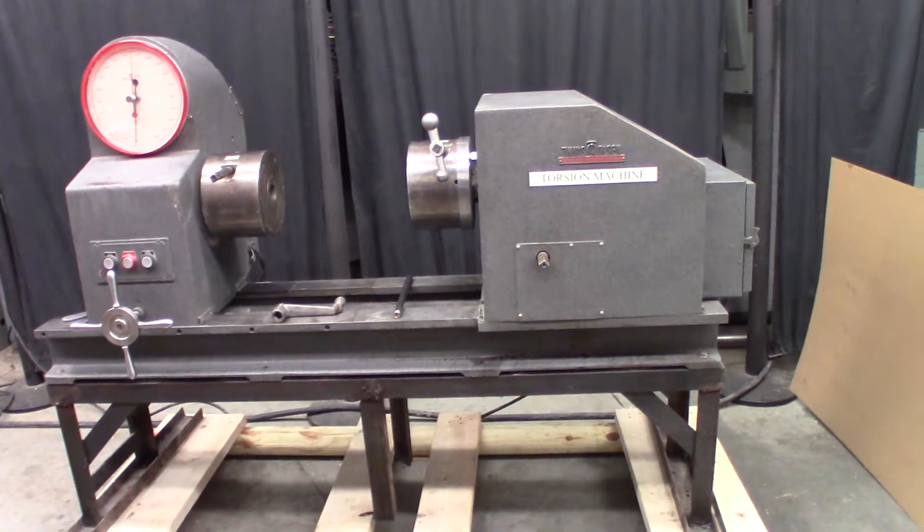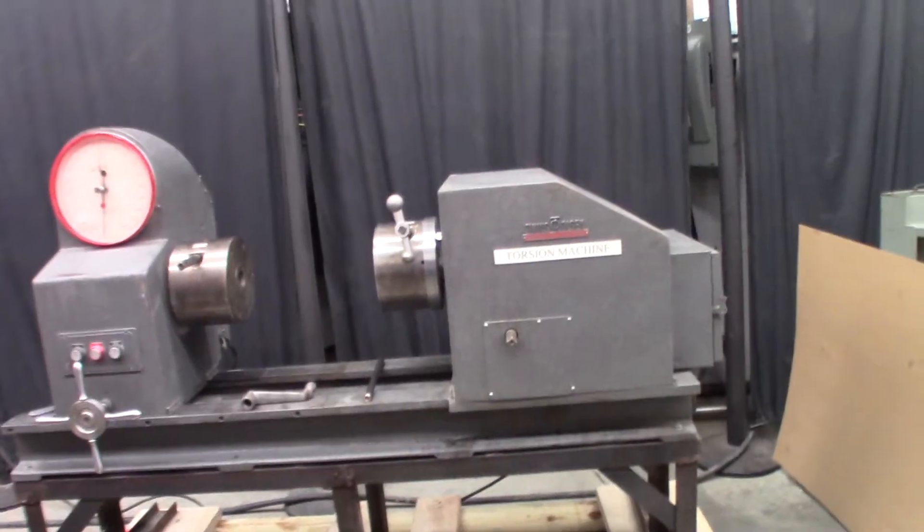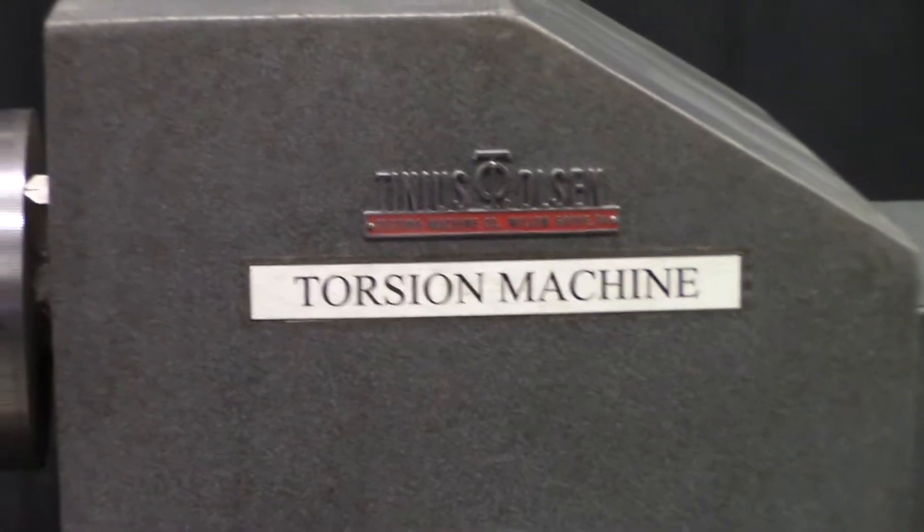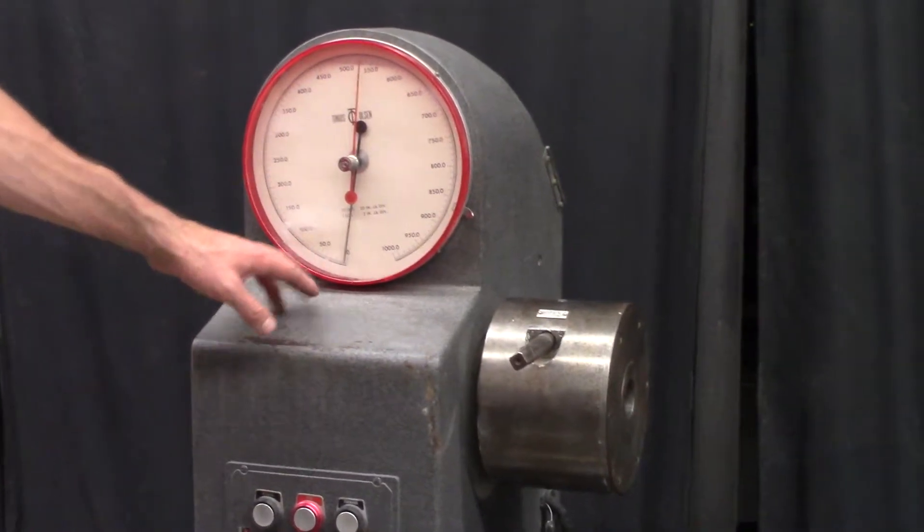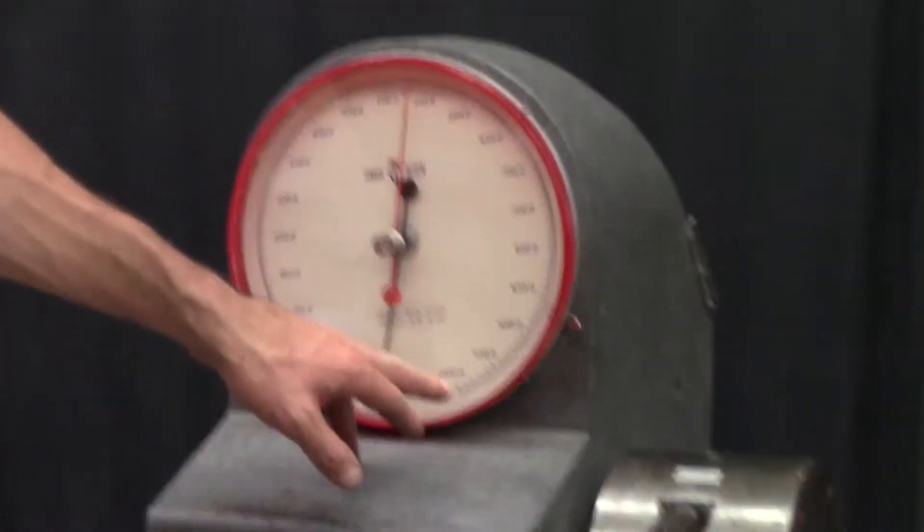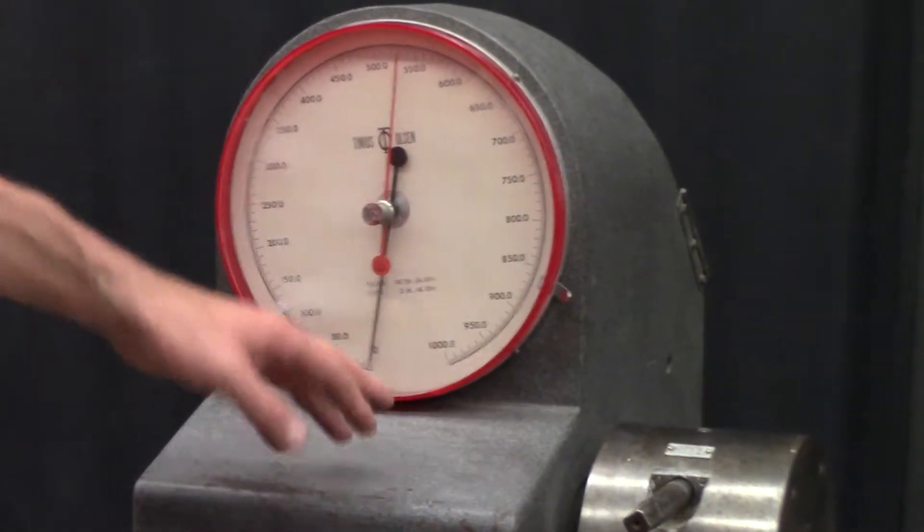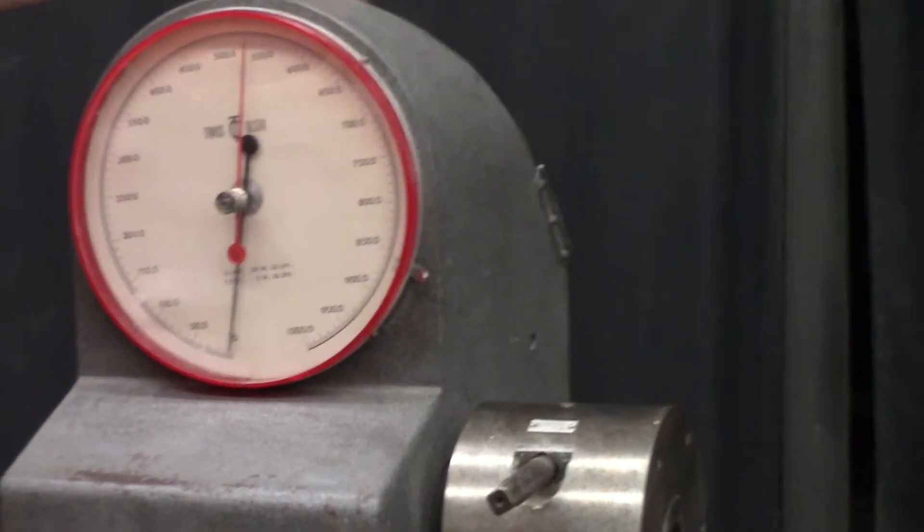Alright, here we're going to do a quick test on this Tinius Olsen torsion machine. This machine has a rating of 10,000 inch-pounds and the gauge is a dual range gauge. It goes from zero to a thousand inch-pounds or zero to ten thousand inch-pounds, and you select that by changing a beam position inside the cabinet. It's a real easy thing to change.